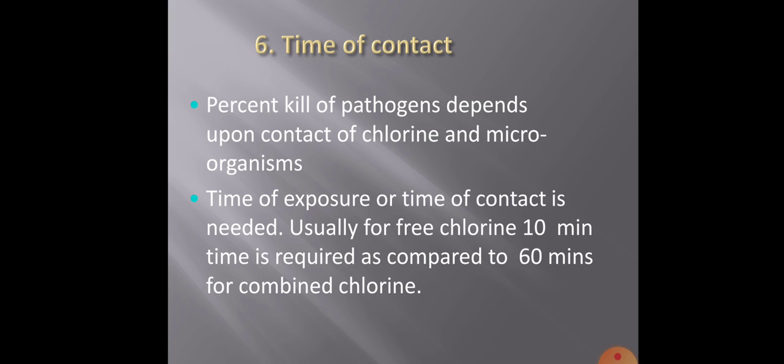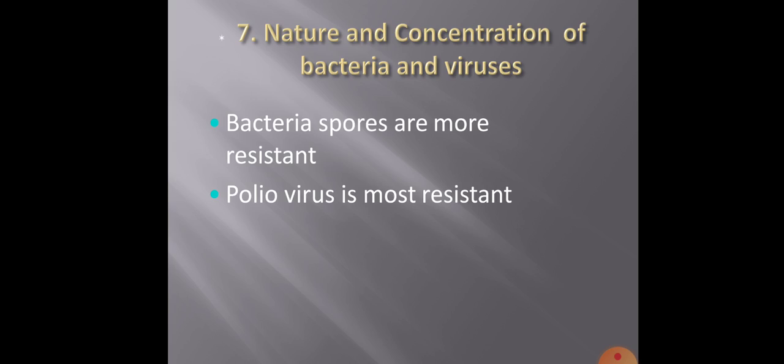Before the water is distributed to the consumers, the time of contact is very much needed, and usually for free chlorine 10 minutes is required as compared to 60 minutes for combined chlorine. So time of contact is another factor which affects the process of chlorination.